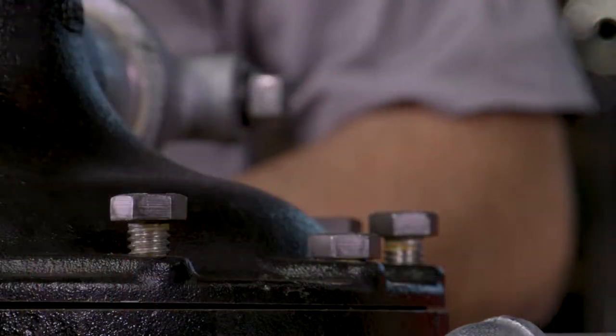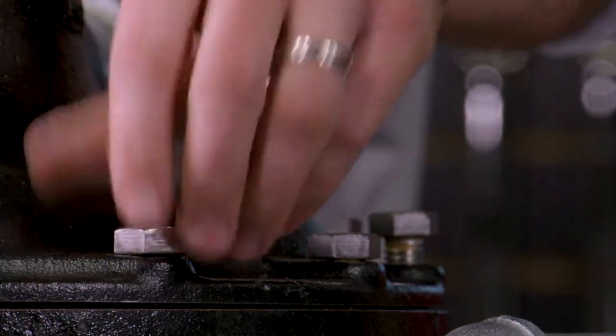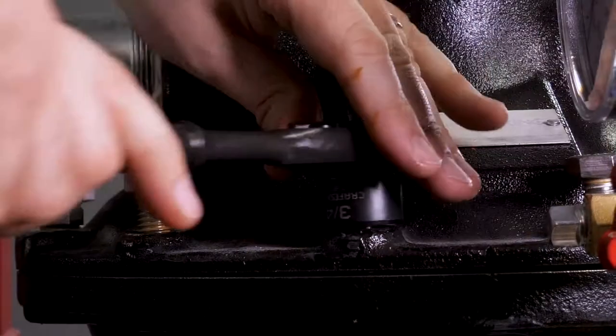Now we can replace the cover bolts back into the valve. When tightening the cover bolts, make sure to tighten them in a star-shaped pattern.